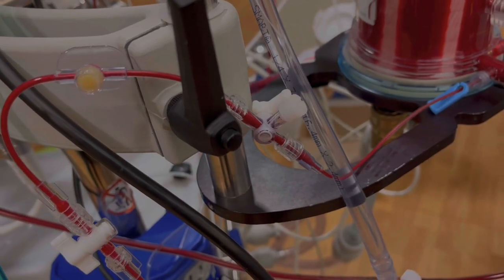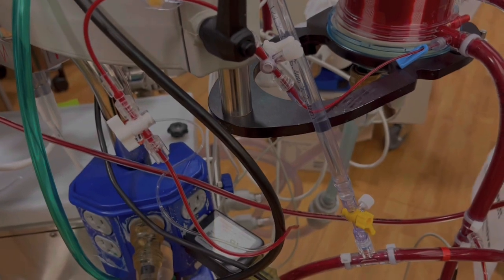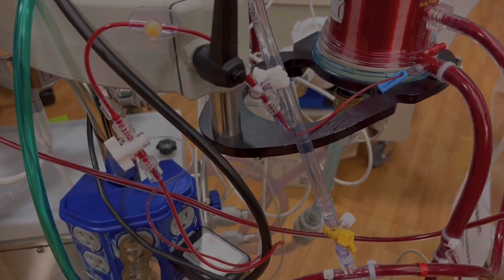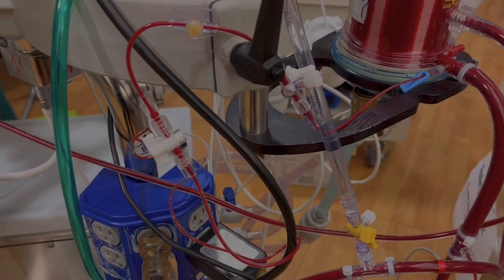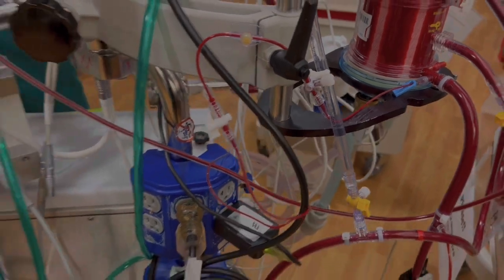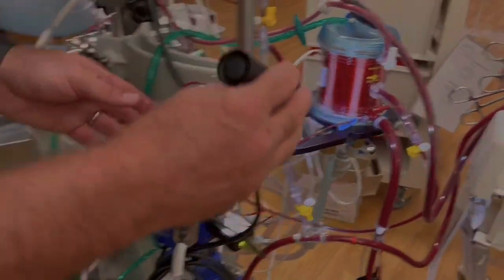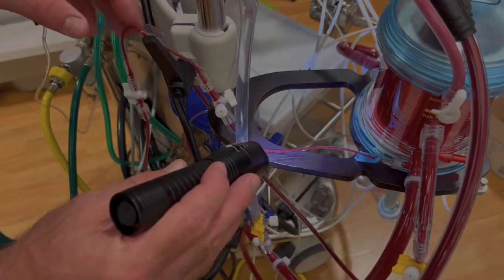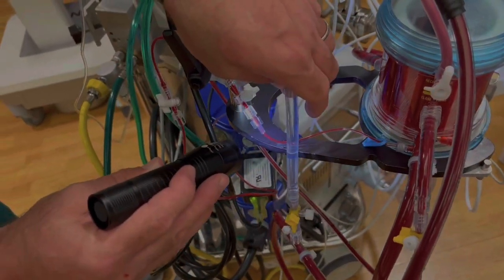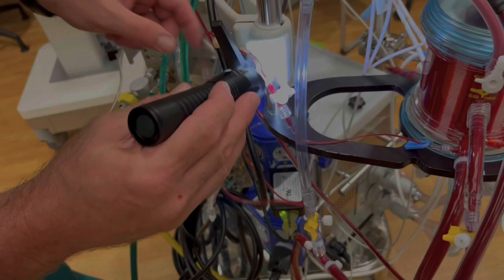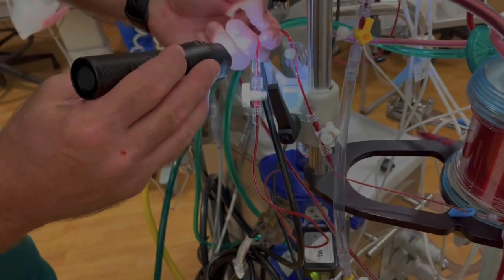This is going to fill our tubing with volume from the circuit, and if there are any clots or fibrin deposits in the tubing, it's going to pull them back a little bit further into the tubing. Next, we're going to grab our flashlight, and we're going to come over and inspect from the circuit back through the post-membrane transducer line, inspecting for fibrin deposits, clots, or air.